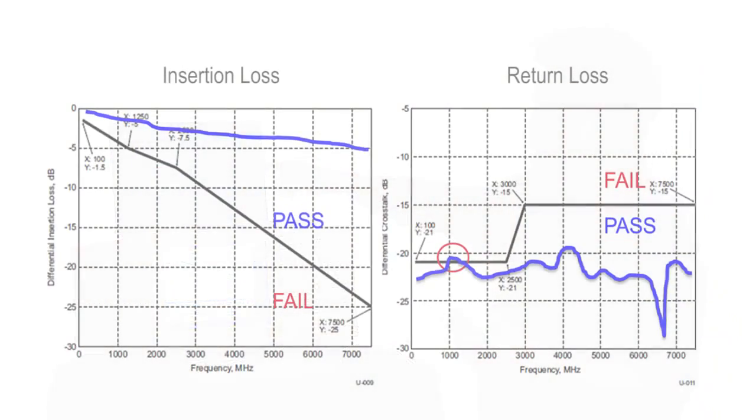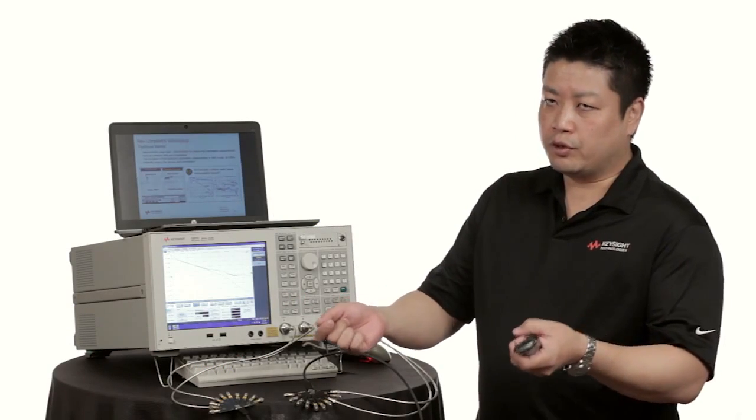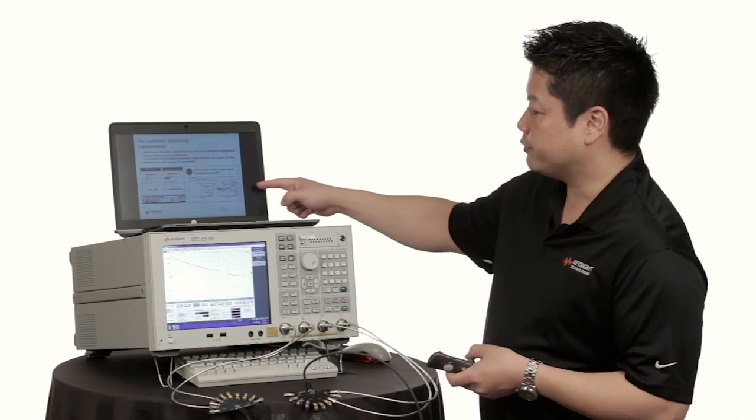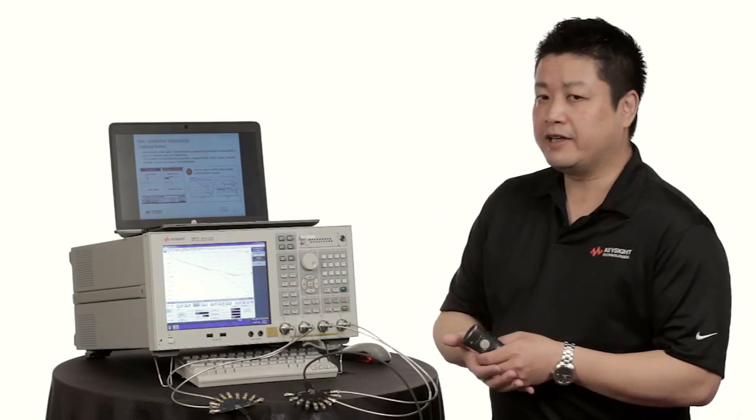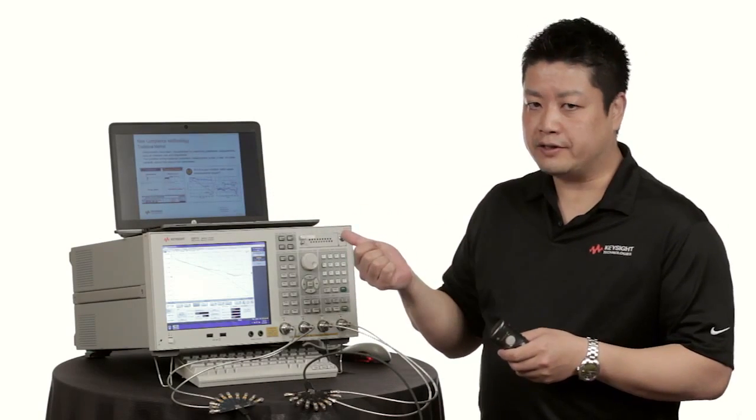Let's say for example you had sufficient margin in the insertion loss and you were failing several points on the return loss trace. When you connected this cable to the system it could very well be that the cable would work without any issues, but according to the specification this is a bad cable because it failed that return loss test.